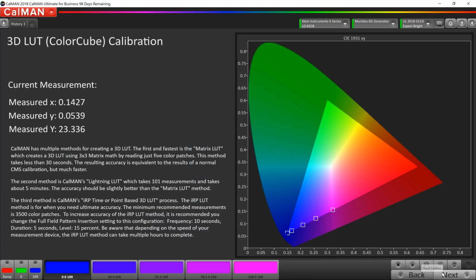Okay, so the 3D lookup table calibration just completed. It took about 4 minutes and 57 seconds, which gave us about 101 readings. And the profile, the last number I saw, it was somewhere between 20 and 30,000 different points that it adjusted. So for the rest of the calibration, we're going to verify those points and make sure that everything calibrated well.